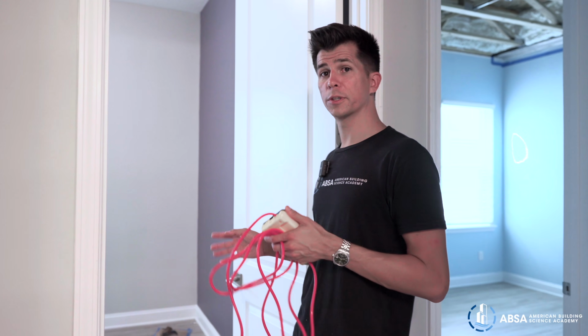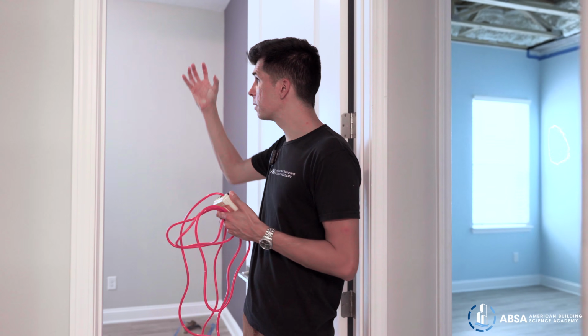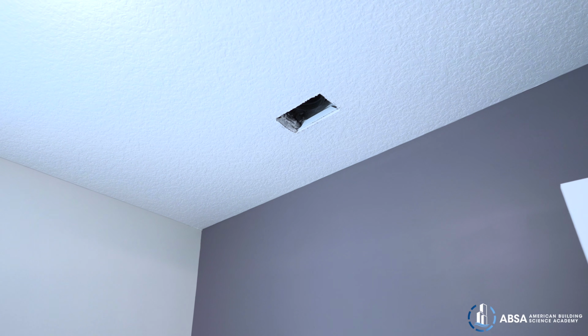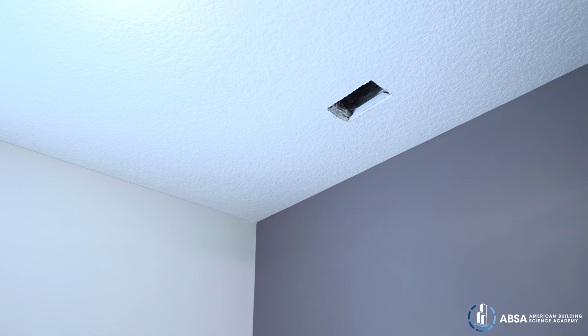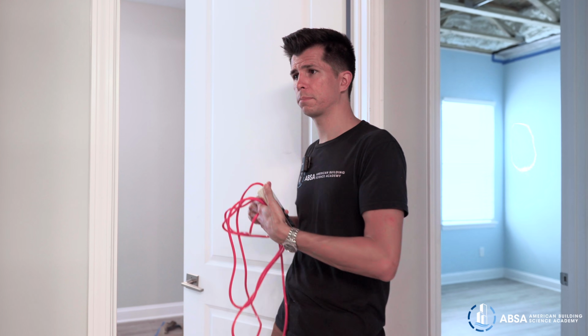While Reagan is getting the duct leakage test set up, I want to check these rooms for return airflow restrictions. There's supply air being added into these rooms, and what happens if I close this door? That supply air is going to be restricted as it's trying to get back to the main return. And that's a problem because it's going to cause comfort imbalances, right? If there's too much stagnant air sitting in these rooms, it can cause humidity problems. It can cause particulate buildup because it's not being filtered. So all of these things are really important for good circulation.